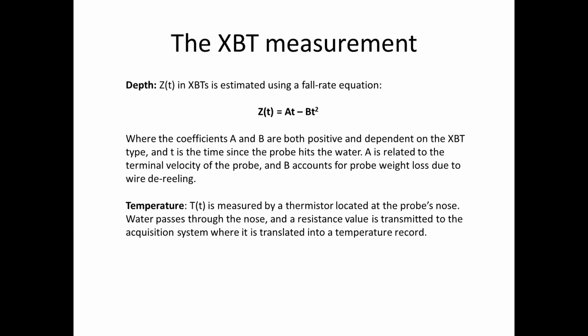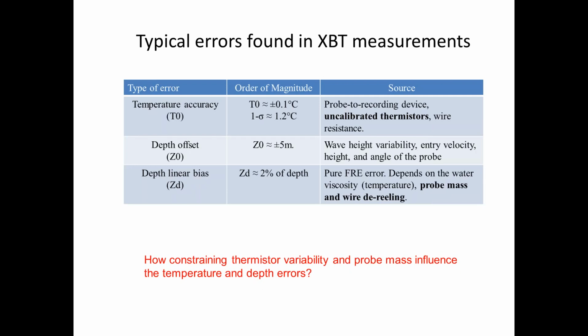And the temperature is measured with the thermistor, which is inside the probe nose. The water passes through a hole in the probe nose and over the thermistor, and that records a resistance that we turn into a temperature record.